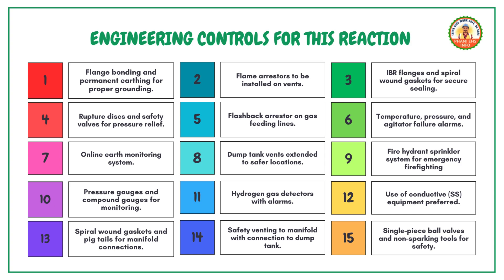Online earth monitoring system; dump tank vents extended to safer locations; fire hydrant sprinkler system for emergency firefighting; pressure gauges and compound gauges for monitoring; hydrogen gas detectors with alarms; use of conductive stainless steel equipment preferred; spiral wound gaskets and pig tails for manifold connections; safety venting to manifold with connection to dump tank; single-piece ball valves and non-sparking tools for safety.